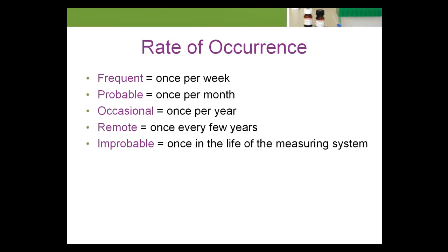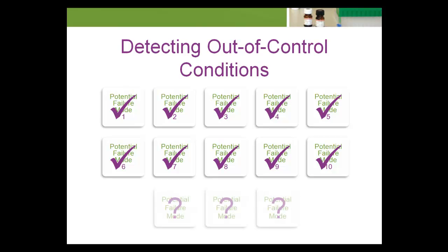The laboratory may identify many potential failure modes in the total testing process that could lead to an out-of-control condition. The lab must then develop a strategy to control the number of incorrect patient results reported. It is advantageous to devise specific control procedures that address each potential failure mode. However, there will always be potential failure modes that are never identified or that cannot be adequately controlled at the point of failure. A lab should strive to minimize the number of out-of-control conditions, but plan for their eventual presence. Statistical quality control procedures based on the periodic measurement of stable QC materials is the approach that has been successfully employed for decades to detect out-of-control conditions.